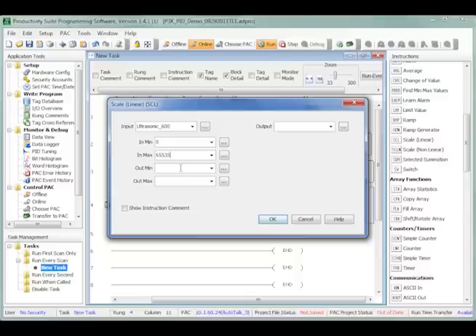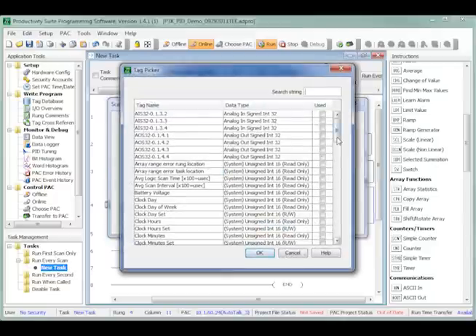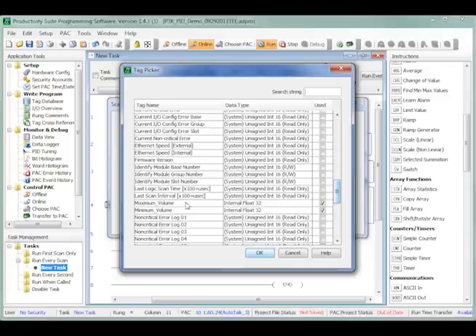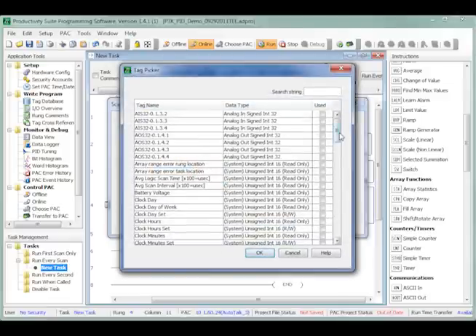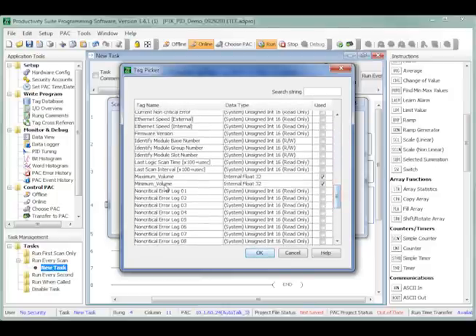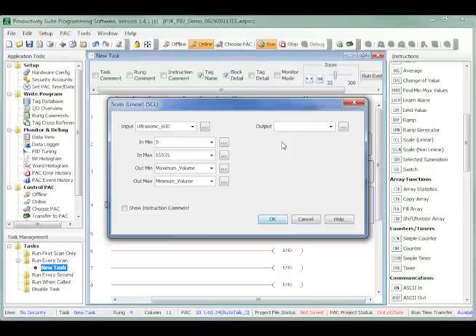The next two parameters, outmin and outmax, become a simple matter of inserting the tag names we created earlier for maximum_volume and minimum_volume. Because our maximum volume is seen when the water is closest to the sensor with the sensor reading 0, and vice versa for our minimum volume, the maximum_volume tag name should be used for the outmin parameter and the min_volume tag name for the outmax parameter. This is a little confusing, but plugging all parameters into one instruction to produce our final results makes programming a lot simpler.